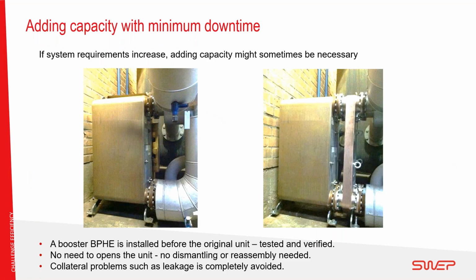One of the questions we get asked about brazed, one of the many questions, but in particular with large heat exchangers, is how do we add extra capacity? This is, of course, one of the features of a gasket plate heat exchanger, that you can add more plates if the system is expanding over time and additional capacity is required. We can't open the brazed heat exchanger. So the solution here is what we call a booster BPHE. This is basically just configured to the additional capacity that's required, whatever that may be. And of course, providing the space to move the existing heat exchanger back, which you would need with any other solution, we can add just a small extra brazed plate pack to give you that extra capacity.